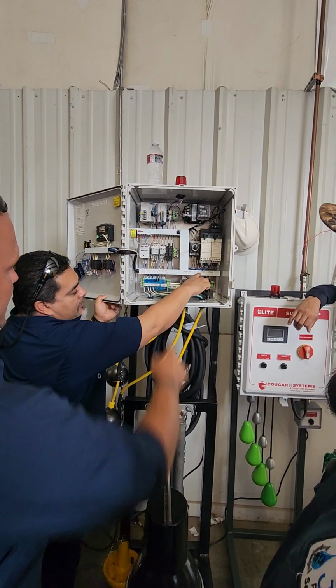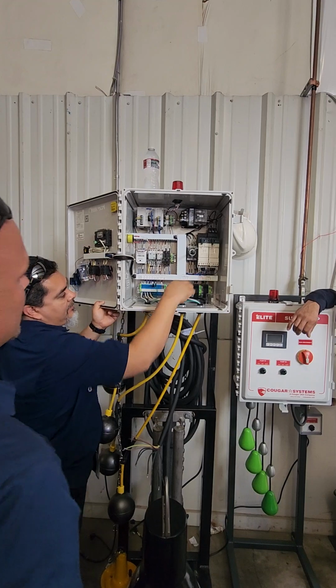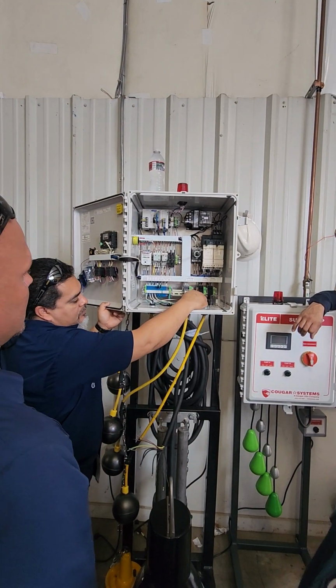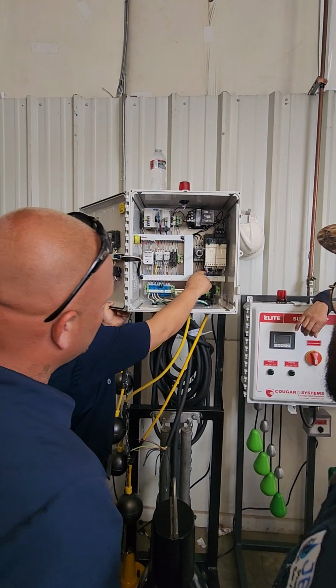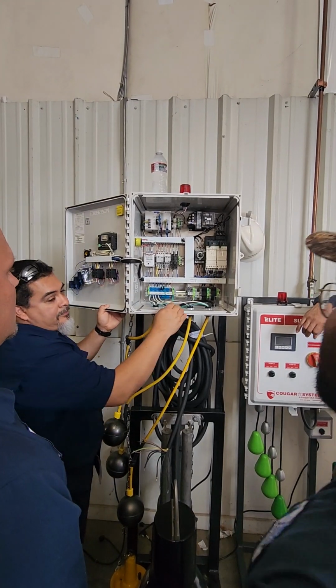Yeah, the power. That's for the floats, okay. Yeah, this is pumps. It's got to be right underneath the pumps. Like I said, we do terminals to hook them in. Sometimes they could just be hooked up directly underneath the contactor. And you can only do that with a 3-phase. 3 phase, yes. Single phase, you can.